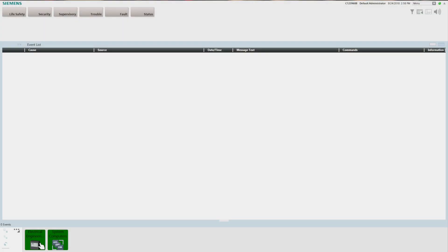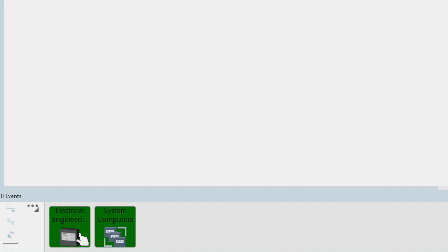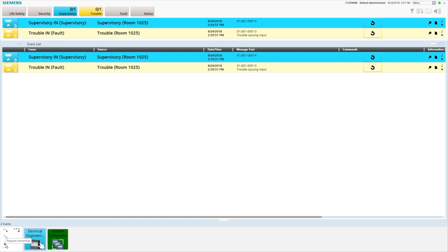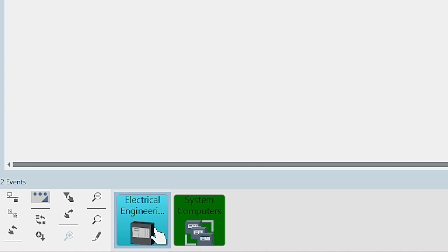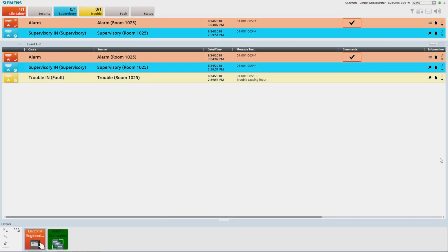At the bottom of the screen is the node map, which displays the status of each fire panel connected to the system, providing you situational awareness at all times. Like the summary bar, the node map is always visible and cannot be minimized or hidden by other windows. When a connected panel is in normal standby mode, the corresponding panel icon in the node map will have a green fill. When the connected panel is in an off-normal state, the corresponding panel icon will have a fill color that matches the highest priority event active on the panel. You can request control of a panel from another operator by selecting the panel in the node map and clicking on the request ownership button in the toolbar. The node map toolbar provides additional capabilities such as disconnect and connect a panel, various sorting and filtering commands, and searching and zooming operations. Note that the event lamps in the summary bar, the event icons in the event list, and the panel icon in the node map will flash and the audio buzzer will sound until the event is acknowledged.